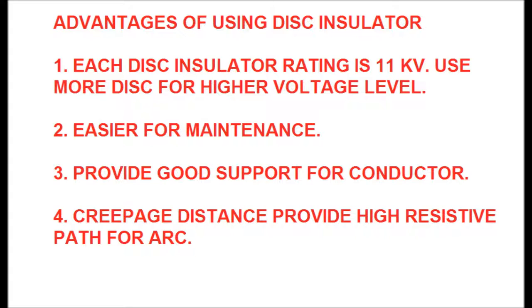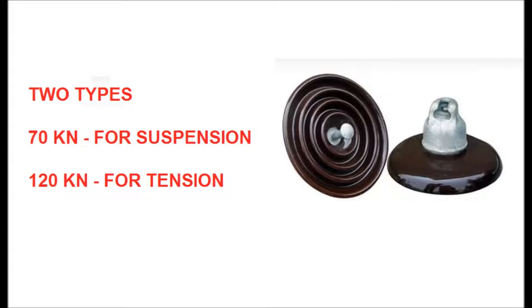There are two types of disc insulators based on material: one is porcelain and number two is glass insulator. Based on use, disc insulators are of two types: 70 kN used for suspension type string and 120 kN used for tension type string.